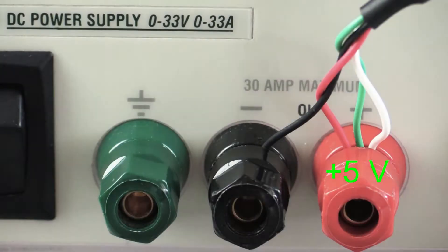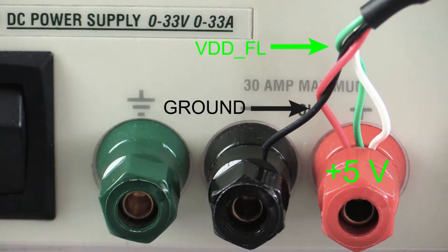Before wiring, ensure the unit will be in the safe operating area. The laser diode driver half cannot dissipate more than 2 watts, and the temperature controller half cannot dissipate more than 9 watts. In this example, we will use single supply operation.